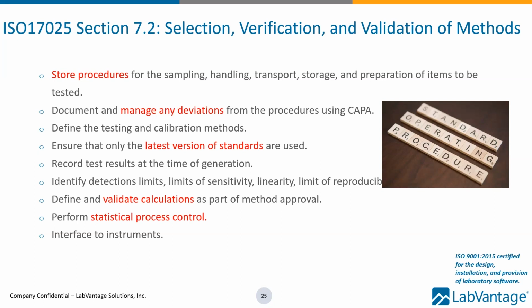Recording test results at the time of generation. And timestamps are also important. The system must automatically apply time and date stamps, as well as who is the examiner that did the work, and those need to be things that are not changeable. When we get into statistical considerations, we're talking about things like detection limits, sensitivity limits, linearity, limits of reproducibility, and then also calculations. I alluded to calculations a little bit at the very beginning.